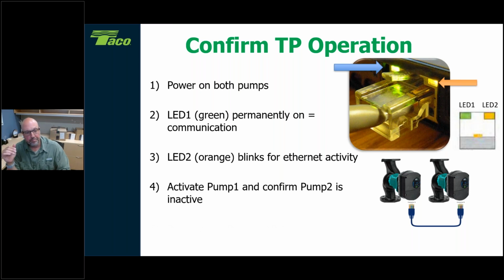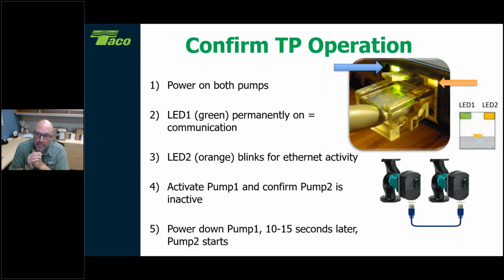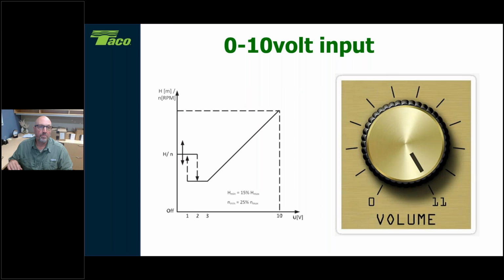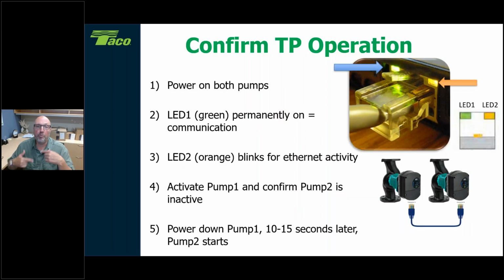Now what I want you to do is physically power down pump number 1. So we do have that service switch right next to the circ. Power it down. Make sure you leave the service switch. So you want 2 separate service switches. Yeah, I ran into that before too. 2 separate service switches. Turn off pump 1. Pump number 2 should kick on in 10 to 15 seconds. If it doesn't, confirm your connections on what you got going on. And then do it in reverse.